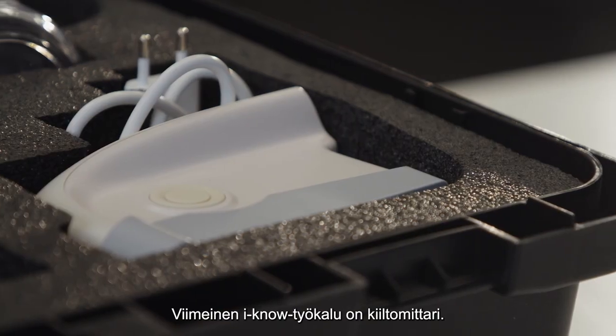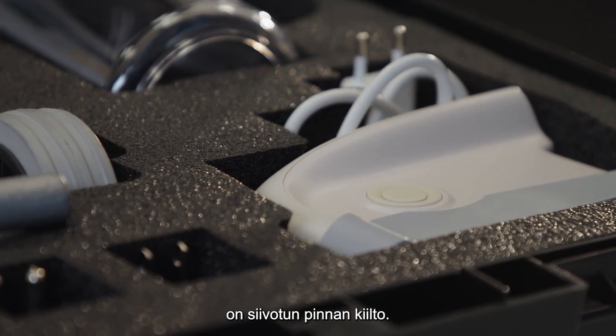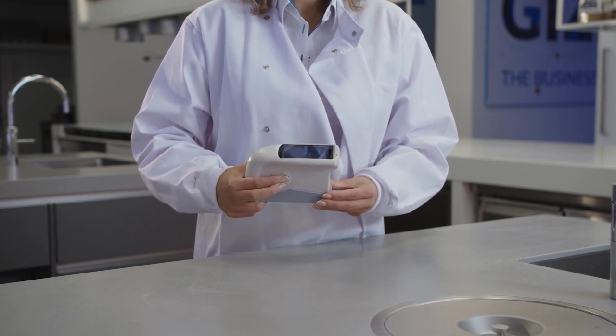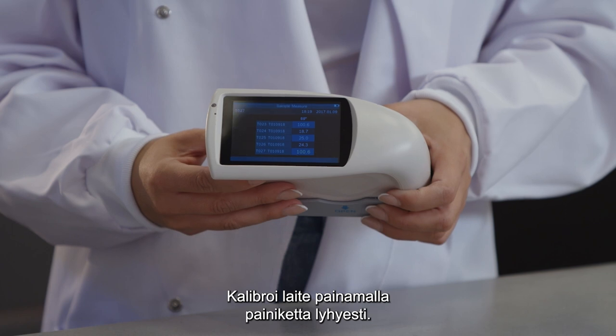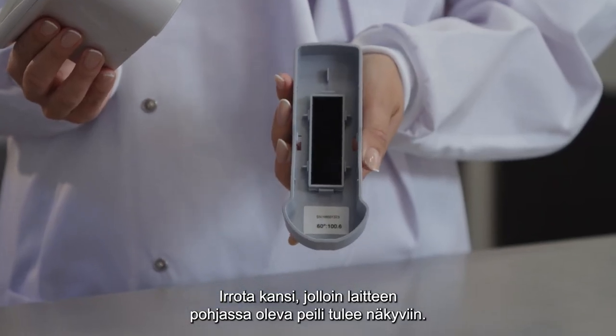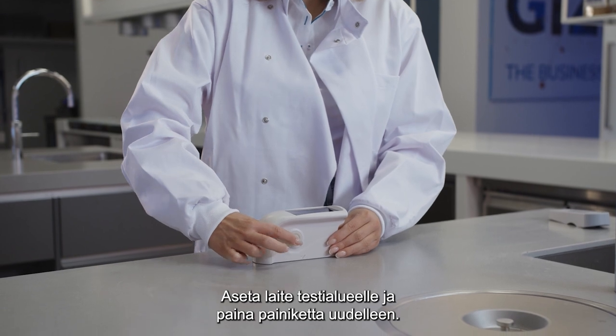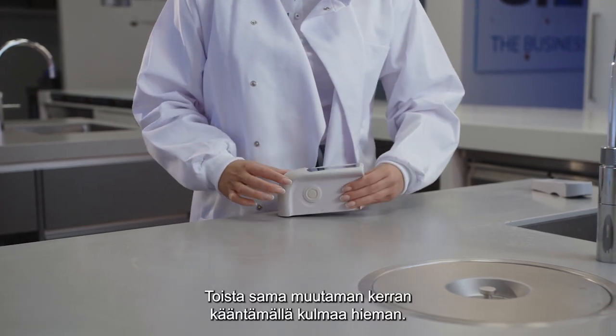The last tool in the i-know kit is the gloss meter. One of the most important visual clues to cleanliness is the shininess or gloss — the gloss meter lets you measure that. Select an area to test and turn on the unit by pressing the on button for 3 seconds. A screen will appear with previous readings. Calibrate the unit by momentarily pressing the button; the screen will now display a gloss reading. Remove the cover to reveal the mirror in the base of the unit and compare to the benchmark reading printed below the mirror. If they match, the unit is calibrated accurately. Place the unit on the test area and press the button again. The unit will display the gloss reading of the chosen test area. Do this a few times from different angles.